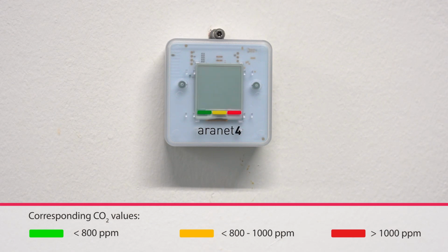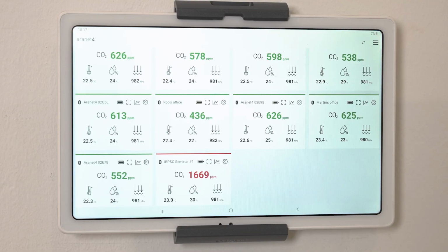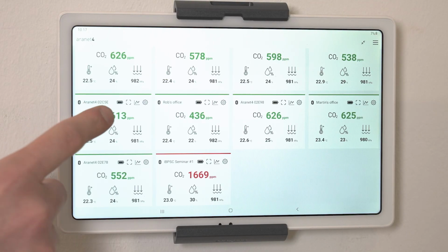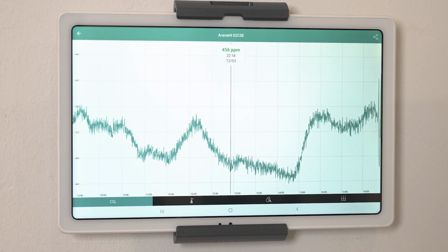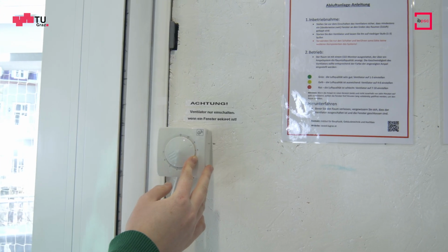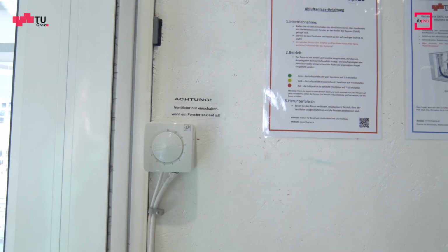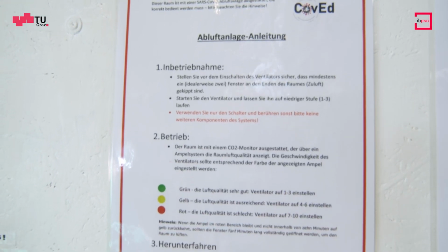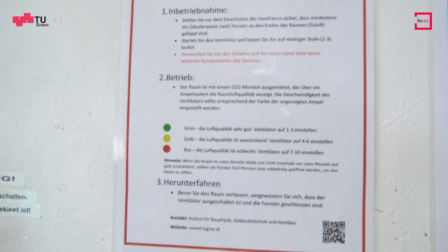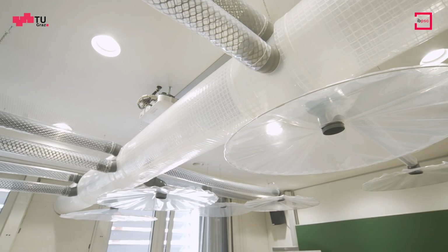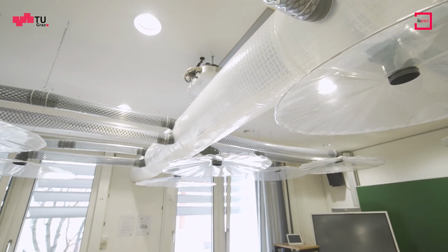It's important to operate the system using a CO2 sensor in the room to give feedback on the air quality, which provides us with a good indication of the risks of viral infection in the room. Finally, it's very important to place a set of operating instructions in the room next to the fan controller and to brief the room occupants on the correct usage of the system.